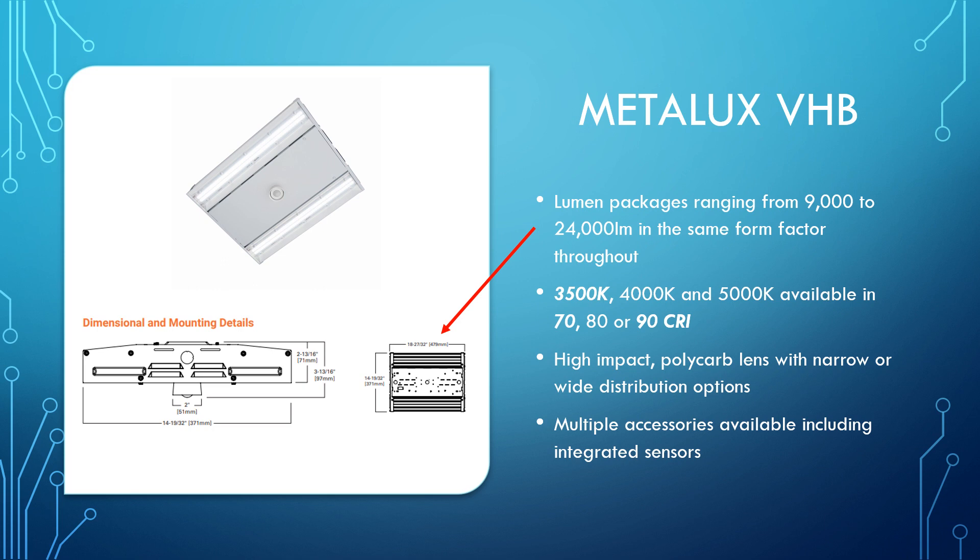You can get a high-impact polycarb lens with this that comes standard, and you choose narrow or wide distribution options. One caveat: if you need emergency lighting, we can only do a remote-mounted 20-watt battery pack, whereas in the LHB you can do a factory or field-installed integral to the fixture. However, unlike the LHB, we can add a ton more sensor options here. If you're looking at going after rebates from the utility companies, I can add a WaveLinx sensor onto the VHB. I can even do a standalone sensor or get this sensor-ready — giving you a lot more options if you're trying to save on energy costs.